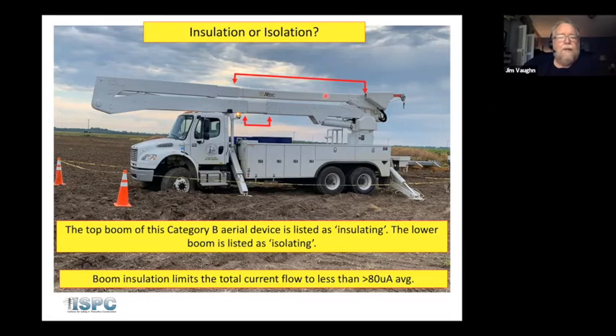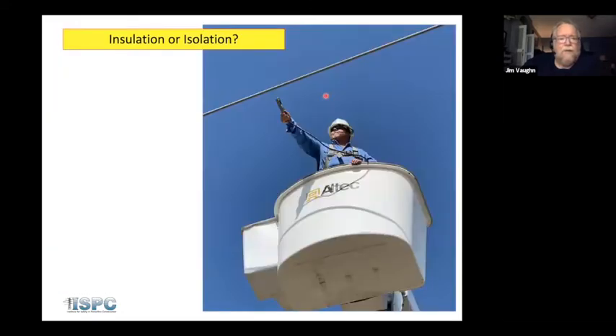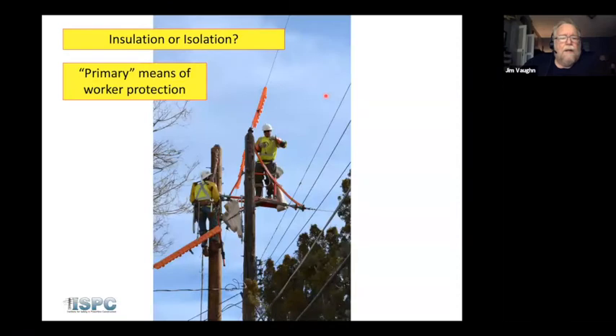In category B, this is simply considered a secondary form of isolation, because your gloves are what's first. Now, this is what we're talking about in category A. We make contact with the phase, we energize the basket, and that basket is isolated from the ground path by the quality of the liner that's in the boom.